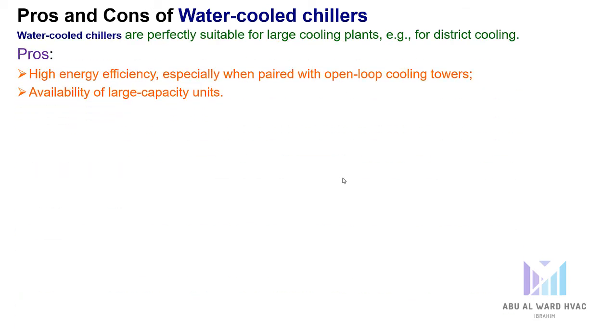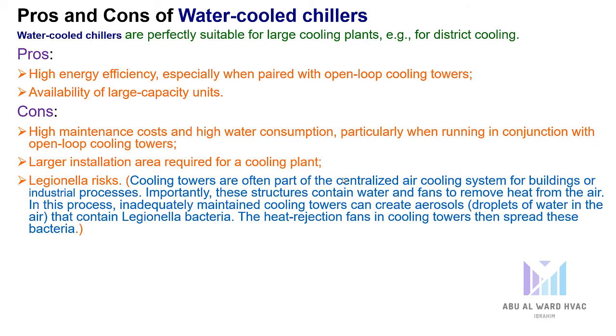Pros and cons for water-cooled chillers. Water-cooled chillers are perfectly suitable for large cooling plants, e.g. for district cooling. Pros: high energy efficiency, especially when paired with open-loop cooling towers, availability of large capacity units. Cons are high maintenance costs and high water consumption, particularly when running in conjunction with open loop cooling towers. Large installation area required for a cooling plant.